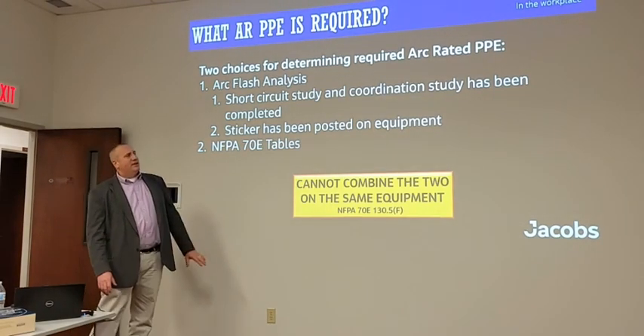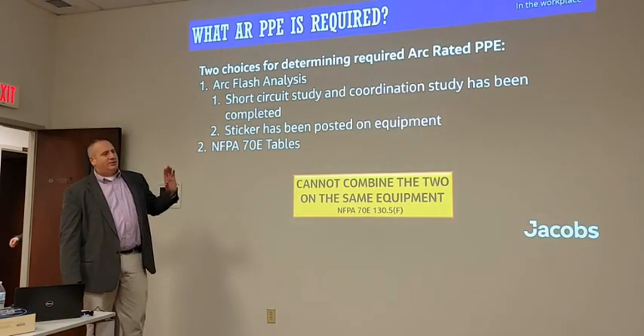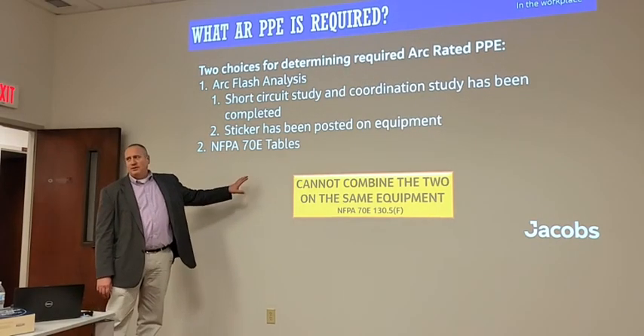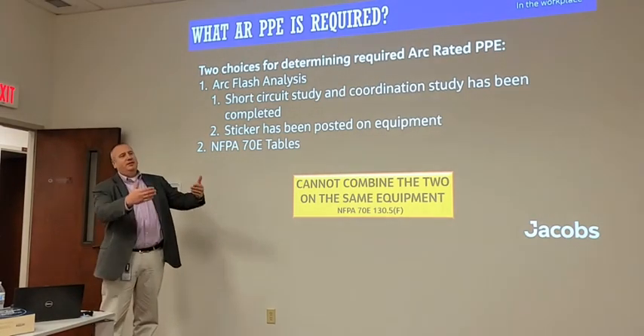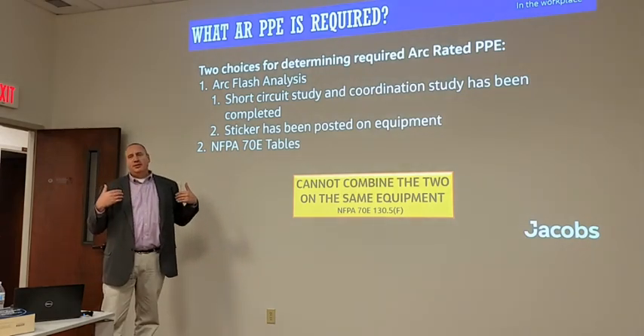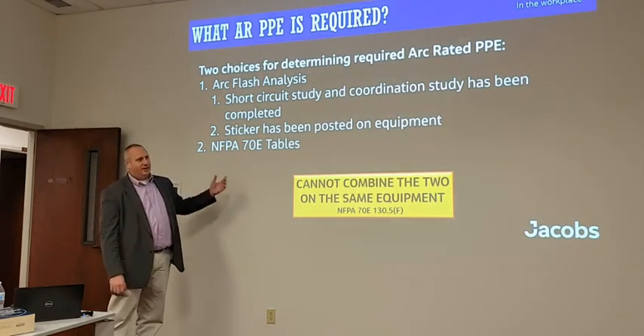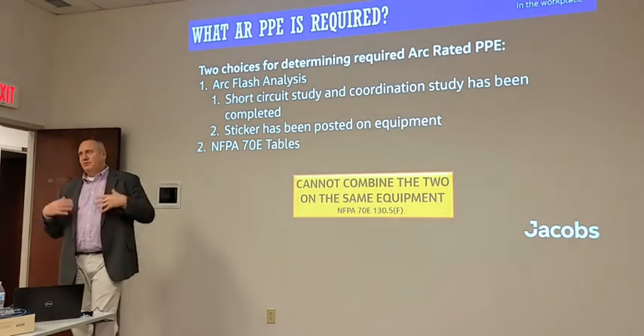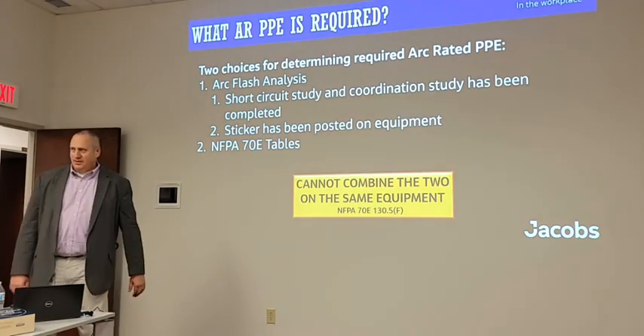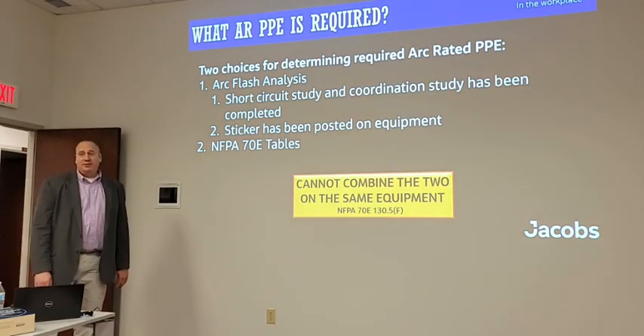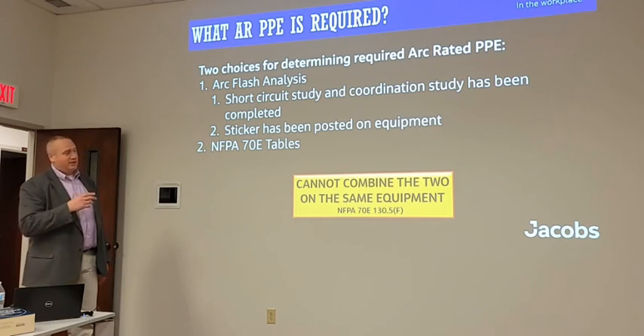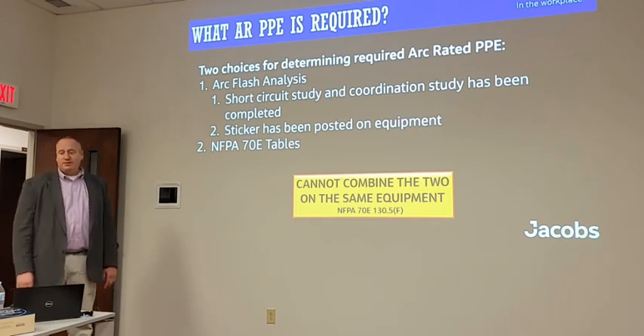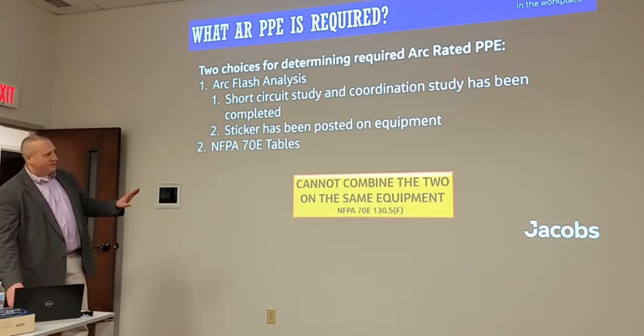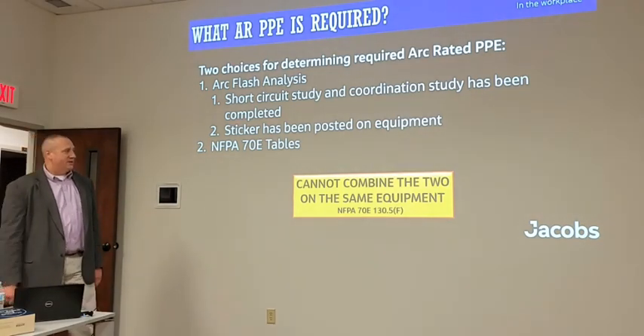Well, let's just say for operations, we're going to go by the tables because it says we don't need PPE. But if we take the cover off of it and expose energized conductors, then we're going to go by the calculation and wear the full suit to protect ourselves from that aspect of it. We can't do that. Once you do the analysis, you've got to go by the analysis regardless of the task that you're doing. So that's what it means by you can't combine the two in the same equipment.